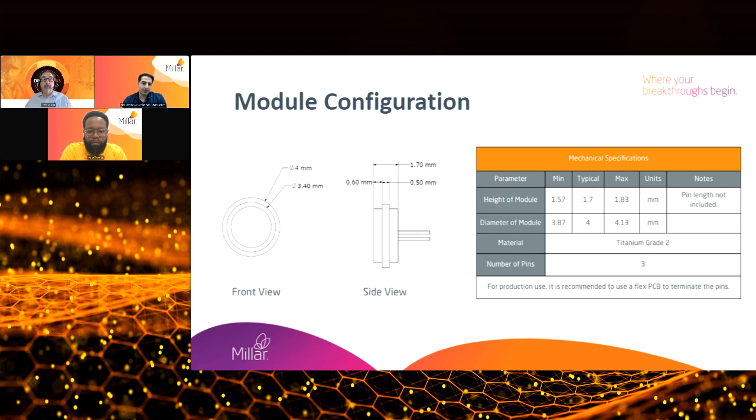But if we go beyond those ranges, let's say for storage purposes, during shipment, cleaning processes, or prototyping or R&D testing, this temperature range can be widened and goes from -5 degrees Celsius up to 30 degrees Celsius, which is quite a larger range compared to what we have around the human body temperature. So even within this large range of temperature, the performance does not degrade. And comparing to long-term use, we expect the sensor to operate within the human body temperature range. If occasionally it goes out of that range, it's still fine, and the sensor will perform as expected.